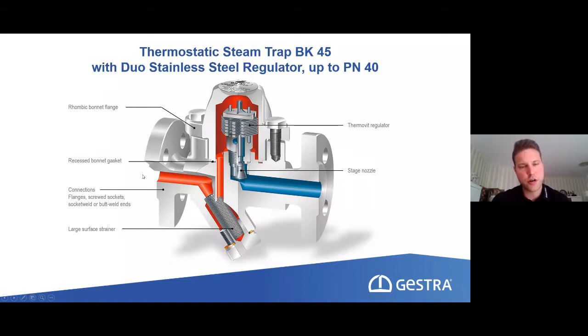So we have the entry of condensate coming from here, then we go through the strainer and then here to the control unit, which senses the current temperature. The strainer itself should be cleaned every now and then. This is something that we recommend in the manuals. You only have to put a wrench on the screw and loosen it, and then you can put the strainer into citric acid, and then it is fine again for another year. You don't have to do it, but we recommend it because this can double or triple the lifetime of a steam trap.